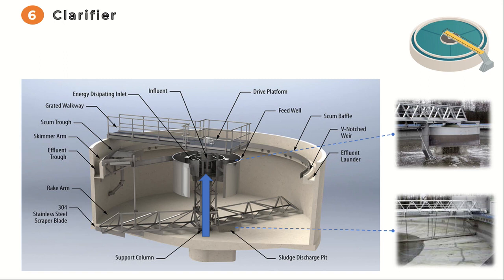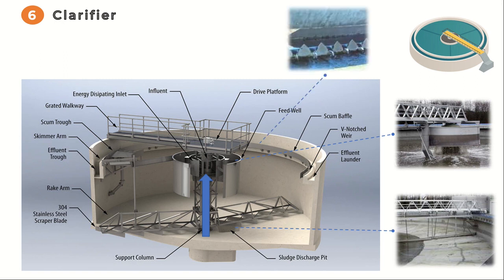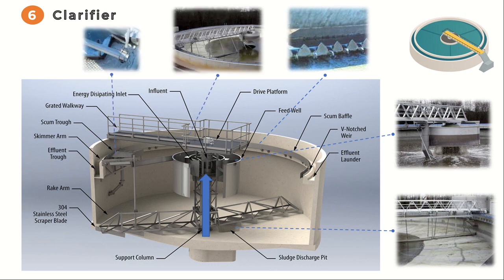To ensure the clarified water exits the clarifier without any solids, effluent weirs are positioned near the top. These weirs allow the clarified water to overflow and be directed out of the clarifier while preventing settled solids from being carried over into the effluent stream. The skimmer, located on the surface of the secondary clarifier, is equipped with a drive platform that moves along the length of the clarifier, collecting floating materials and scum.